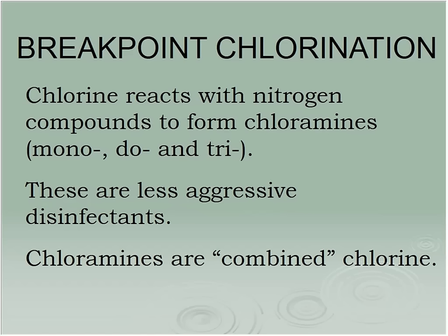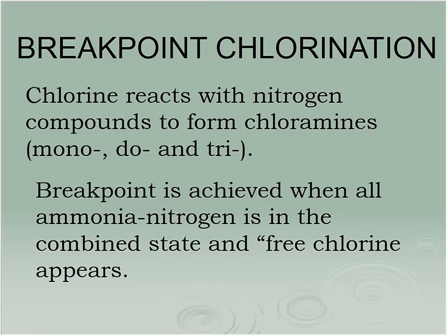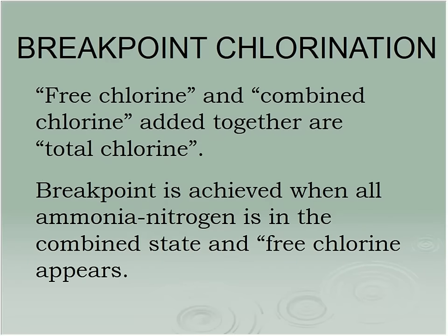We've got a lot of other different stuff, such as nitrogen compounds and various other things that react with the chlorine. Chlorine's a very strong oxidizer, so if there's something around to react with, it'll do it. And if we have nitrogen compounds in there, they'll form chloramines, which will still do some disinfection, just not as effective. It's called combined chlorine. But this breakpoint idea takes a little while to finally grasp the whole thing. It took me a couple of years before I fully understood what the heck they were talking about.